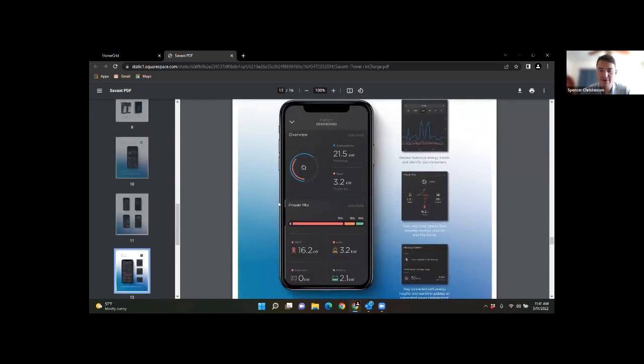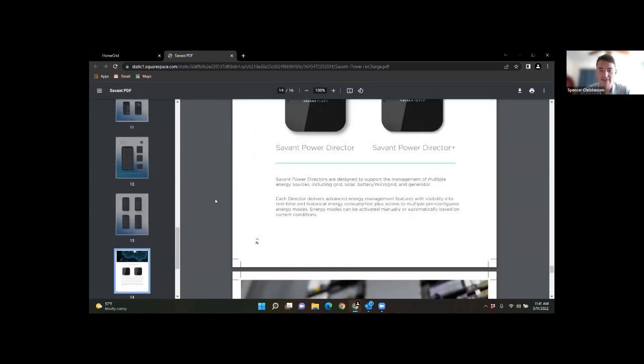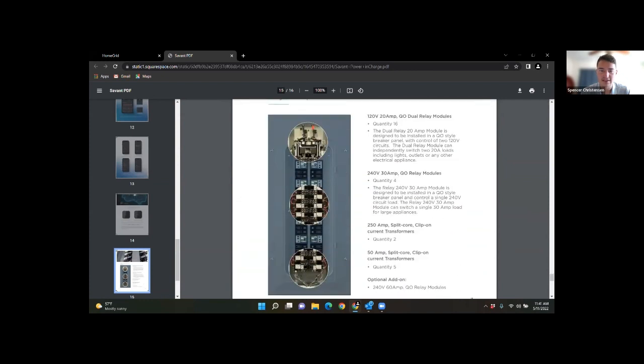The commissioning is very simple too. Instead of one of those other smart load systems that can take a full day on a retrofit, sometimes 2 days, this is definitely under 1 hour for installation and commissioning. So very exciting — this is how it ties in. You can use CTs to do full home energy audits. I think this is the direction smart load is going to go for retrofits especially. They have 60 amp companion modules.